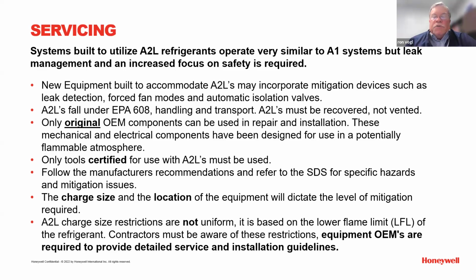You may or may not be aware that when you charge a refrigerant, even an A1 like 410A, the lubricant you're using is miscible, meaning the refrigerant and oil like to mix. So if you charge a system, some of the refrigerant ends up in the lubricant, and it's the same with A2Ls, except now you've got a flammable component. So you break open a system, do a quick vacuum, and start brazing on it. As the temperature goes up, the oil can outgas and release the refrigerant. Not a huge deal with an A1 refrigerant, but on the other hand, I have started R22 and mineral oil on fire. So it's going to be exacerbated by an A2L.